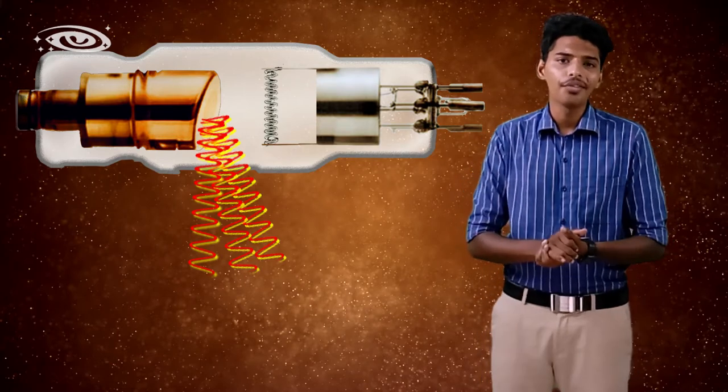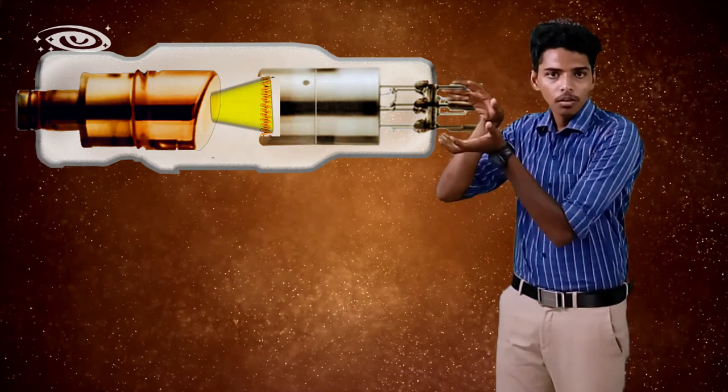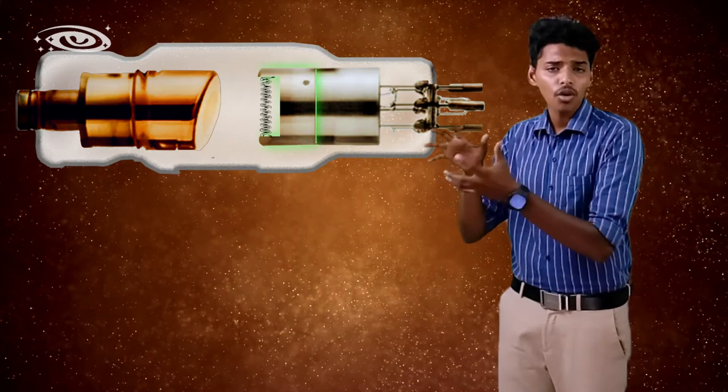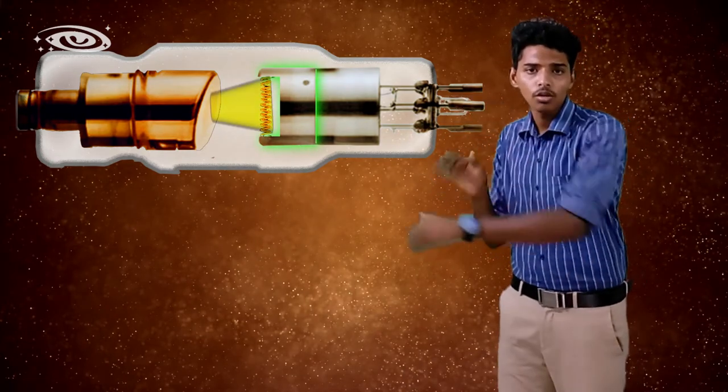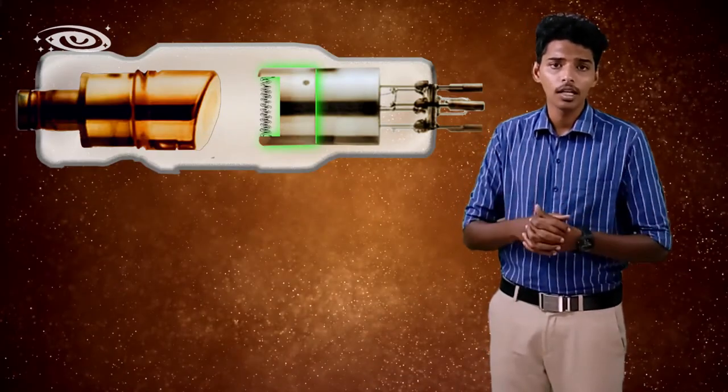For this reason, we focus the electrons by using a focusing cup. We give an additional strong negative charge to the focusing cup to focus the electrons to the focal spot. This is the reason for using a focusing cup in the cathode.